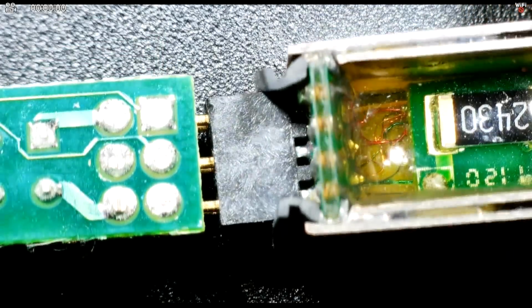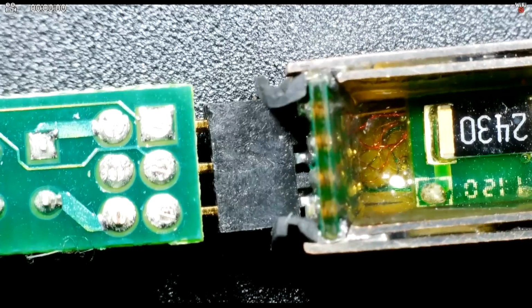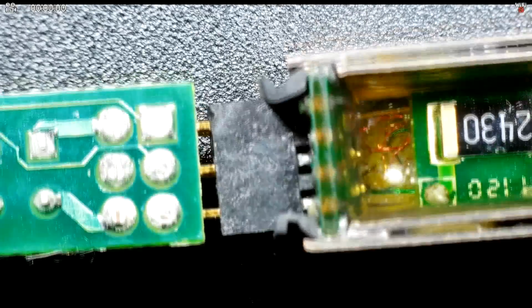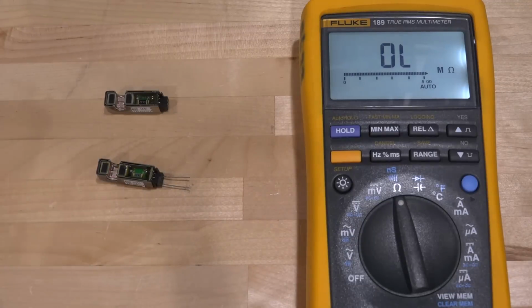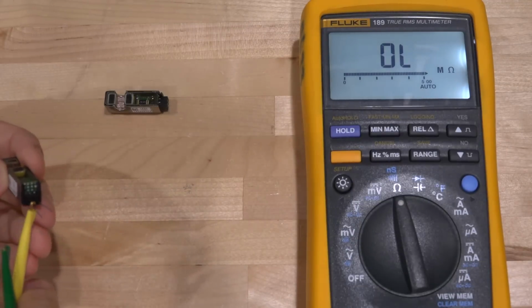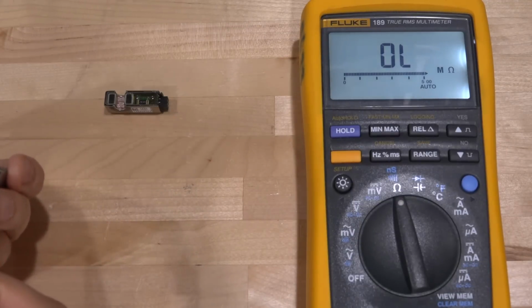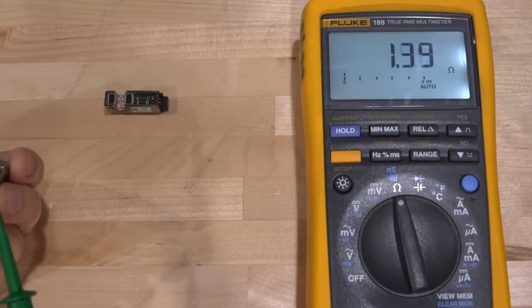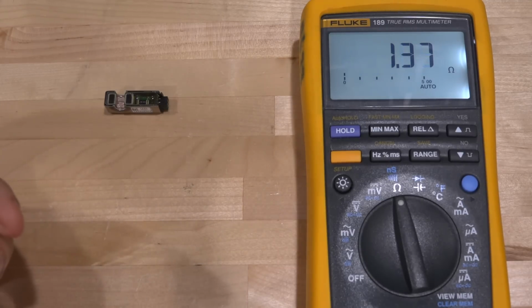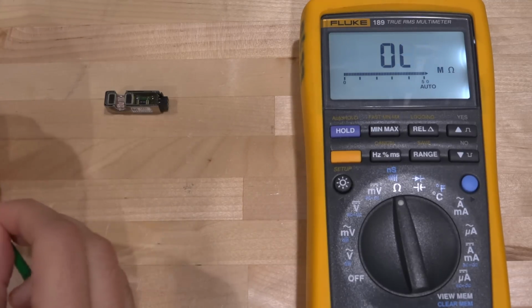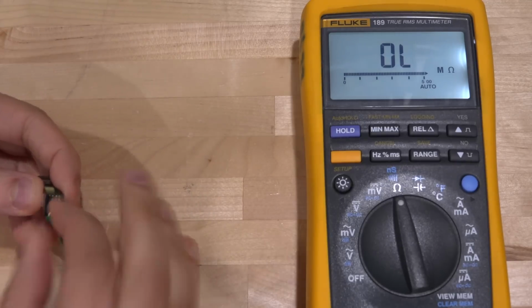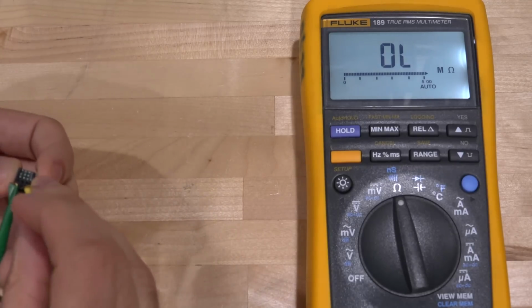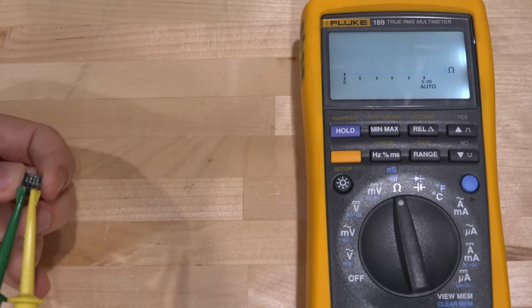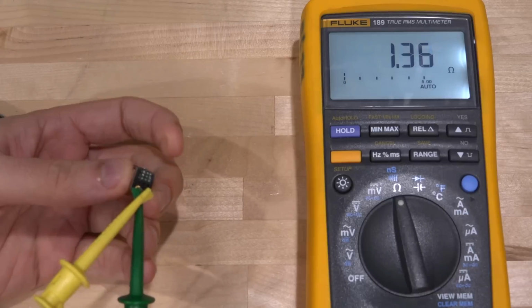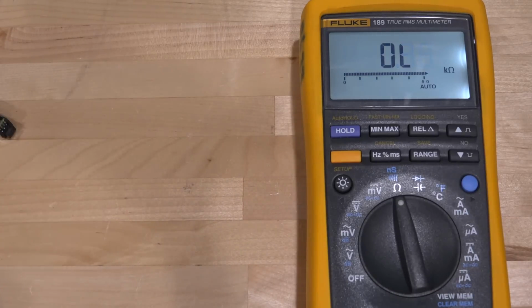So using that, we should be able to do some relative measurements between these two transformer heads and make sure all the components are actually there. And from there, hopefully, we can draw some conclusions. Okay, let's see what we have here. So here are the wires of the working transformer, primary or secondary, whichever one you want to call it. And we have 1.4 ohms. So that looks good. And I can take this exactly and plug it into the one that doesn't work, and we should be getting something similar. Look at that, 1.4. Okay, so that means that the transformer windings are actually working.